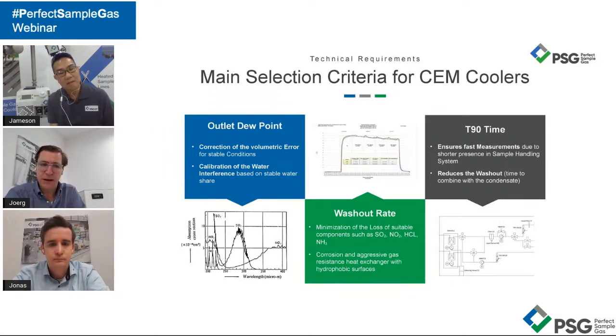The last criteria, maybe also something important, is somehow connected to when we talk about the heat exchanger. The T90 time means the time it takes in the sample handling system. Remember the P&ID from before, where calibration gas is given at the top at the gas sampling probe, and it finally reaches 90% of that value on the analyzer side. That's characterized as the T90 time. This is very important, since it means how long the gas stays in the gas conditioning system, in the gas cooler, in the heat exchanger.